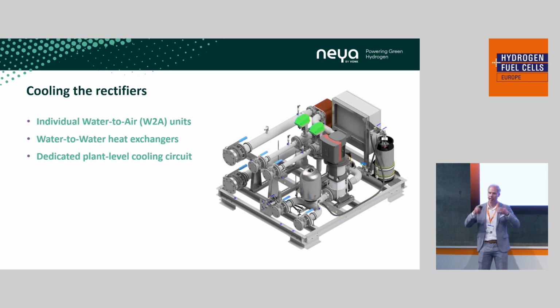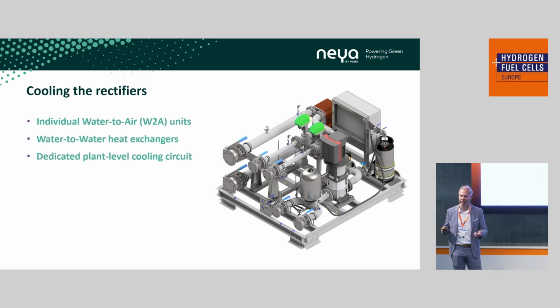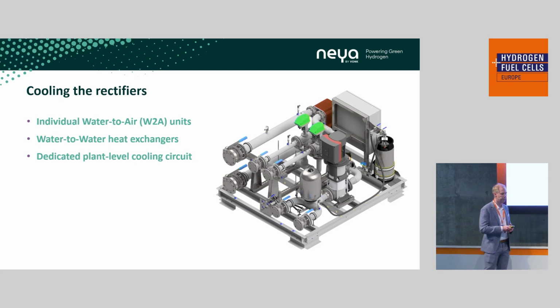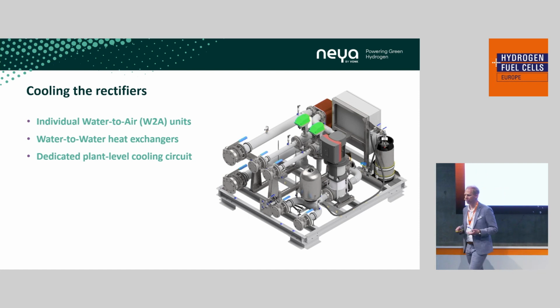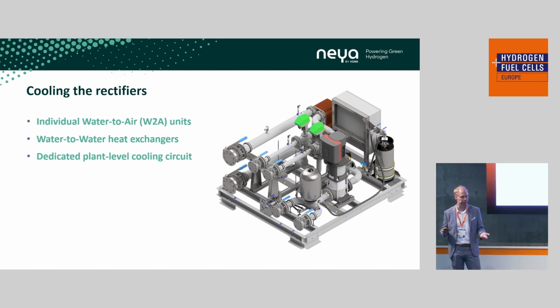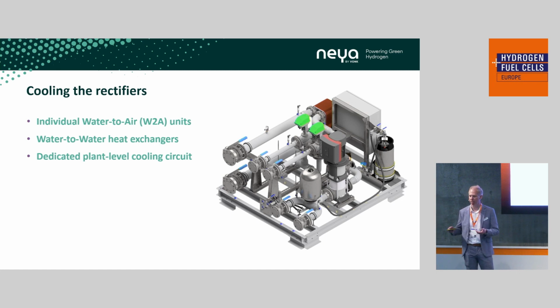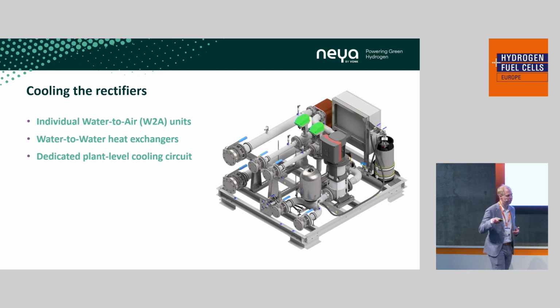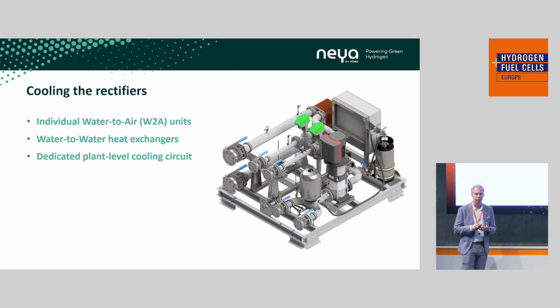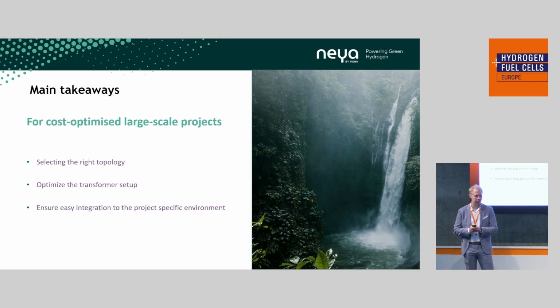However, if you're scaling bigger, with 10 or 20 such rectifiers in place to meet hundreds of megawatts of power, it can be quite interesting from a commercial point of view to set up a dedicated plant-level cooling circuit just for your rectifiers, with their specific cooling temperatures and water characteristics. All these things should be considered when trying to achieve the lowest cost on a project level.